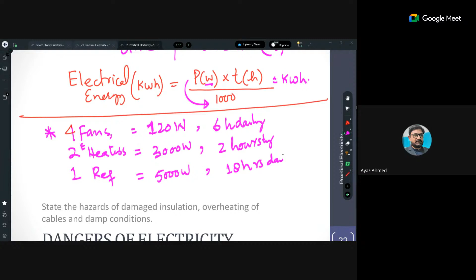What will be the total electricity consumed in kilowatt hour? So what will you do? You will find the power consumption. 120 into 6 divided by 1000, because that is in hour, multiplied by 4 since the fans are four. Plus 3000 into 2 divided by 1000, multiplied by 2 since the heaters are two. Plus 5000 into 10 divided by 1000.